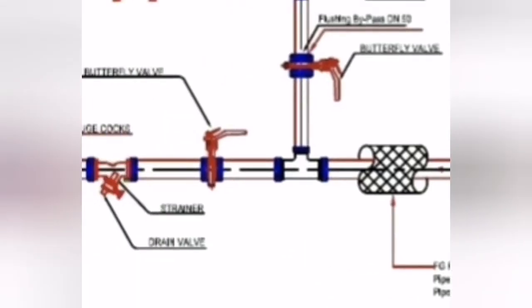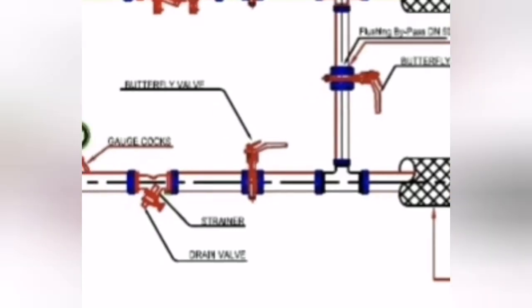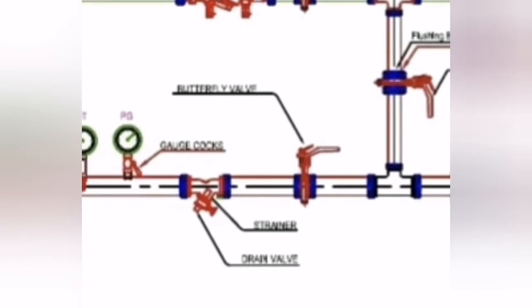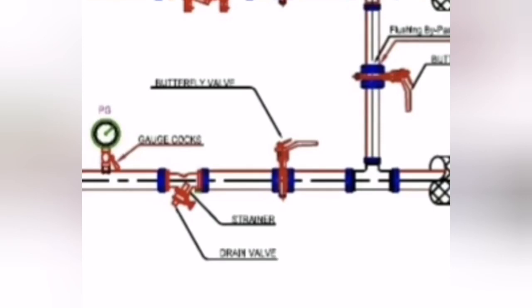After this, there is a T installed on the suction line which connects the bypass line. I will explain later what the function of this bypass line is. The third one is the butterfly valve. A butterfly valve is used to stop the flow in certain cases, when you want to disconnect the AHU or change the strainer. That is the basic need for the butterfly valve. Here you can also use a gate valve, which functions like a butterfly valve.